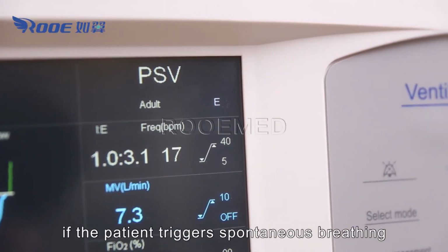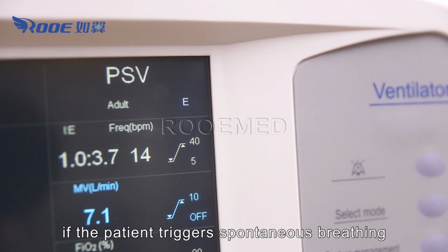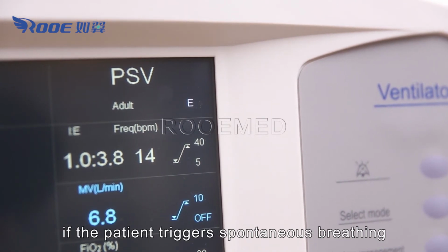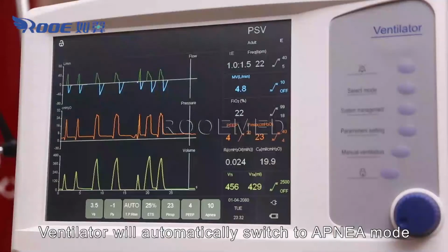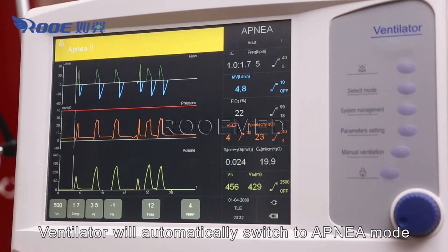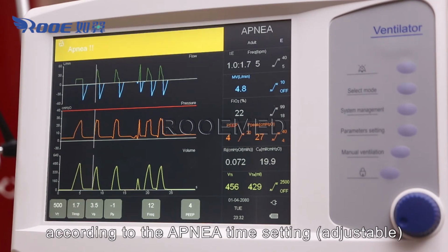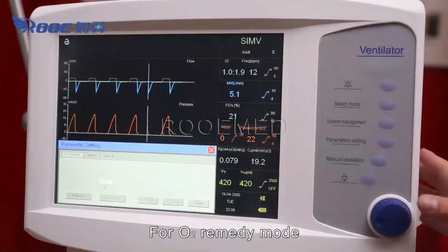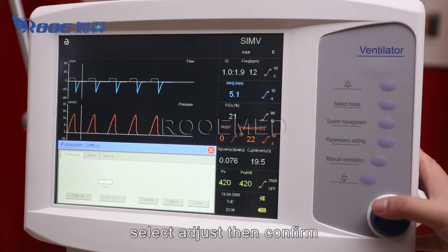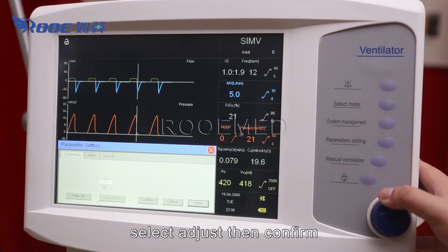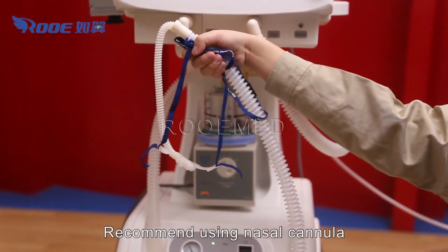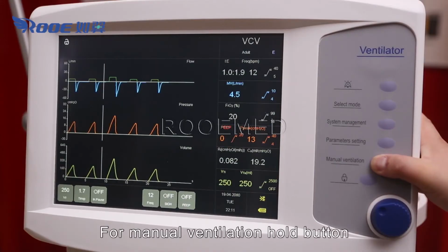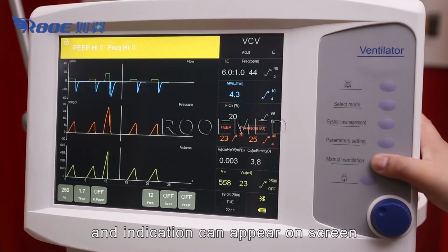Spontaneous breathing icon is active if the patient triggers spontaneous breathing. The ventilator will automatically switch to apnea mode according to the apnea time setting. For O2 remote mode, scroll down to the second page of parameter setting. Select adjust, then confirm. We recommend using a nasal cannula. For the manual ventilation hot button, an indication can appear on screen.